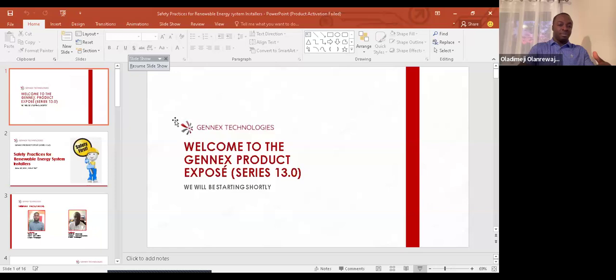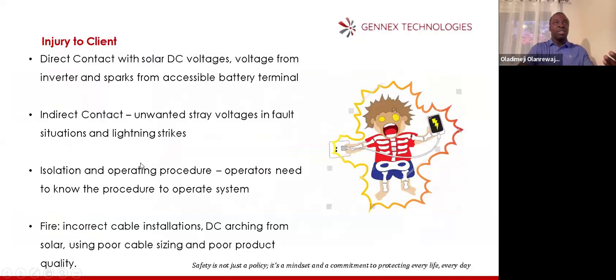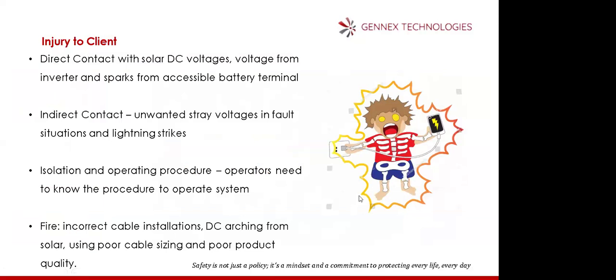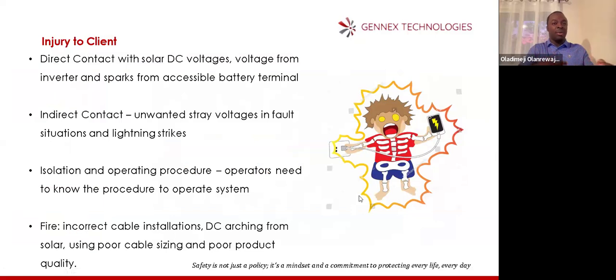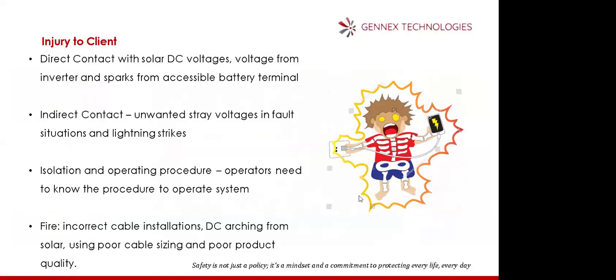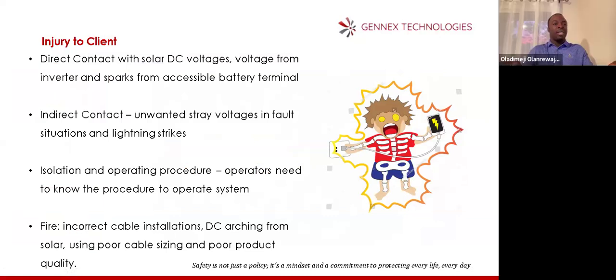When, let's say, a battery cable, you use a cable of 6 mm where you ought to have used, let's say, a 16 mm cable. Once the cable cannot carry the intended load on it, then it starts to get hot. And that is the start of fire. When it gets to a point where it can't hold it anymore, then it catches fire. And those are things that we need to look at carefully so that we keep our clients safe, we keep our installation safe, and also we keep ourselves as installers safe.